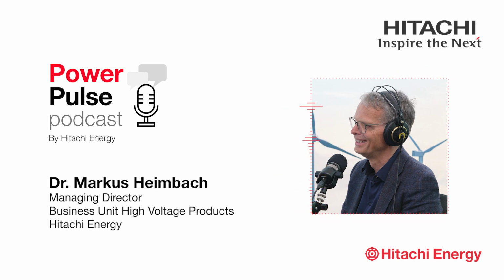We use in high voltage a beautiful gas from a technology point of view, called SF6, sulfur hexafluoride, which is the best gas you can imagine for insulation and for interruption. We need the circuit breaker to interrupt the current, especially the fault current or short circuit current. And when you interrupt the current, you need a gas which cools down the arc. The interruption is done by an arc, and you need a gas which cools it down as fast as possible in order to withstand the voltage after the current zero.